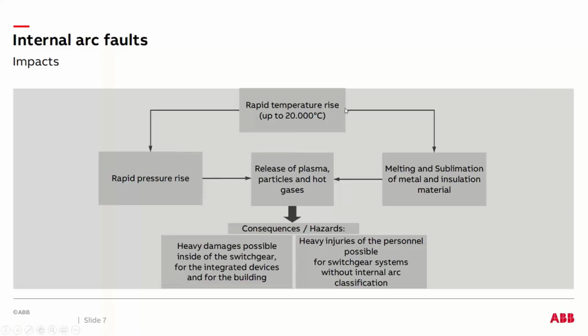A quick overview, right? When you have an arc flash event, it actually goes through a high impedance, because the arc flashes over through air, and instantly you have a really, really high temperature of about 20,000 degrees centigrade being developed inside your switchgear, that could lead to two different phenomena. One is the rapid pressure rise, and the other one is the melting of the metal of your switchgear and becoming a ball of fire, right? So those are the two after effects when an arcing fault initiates in your equipment, right?